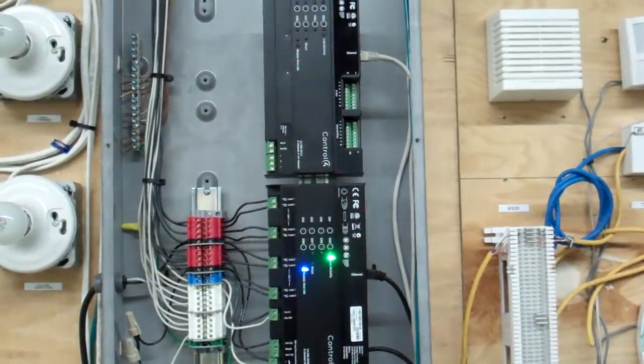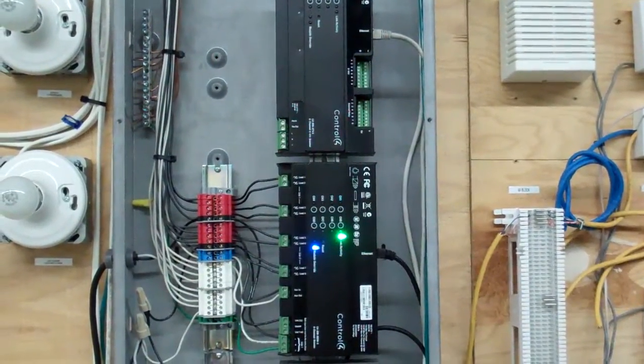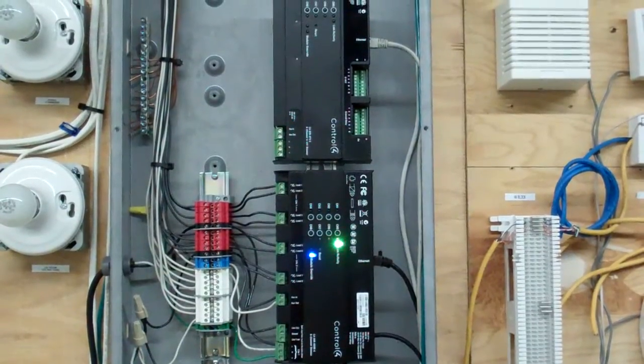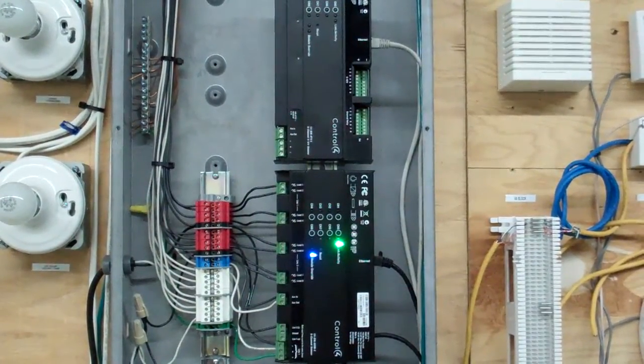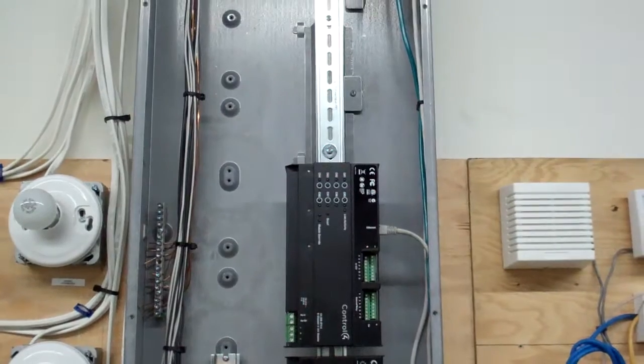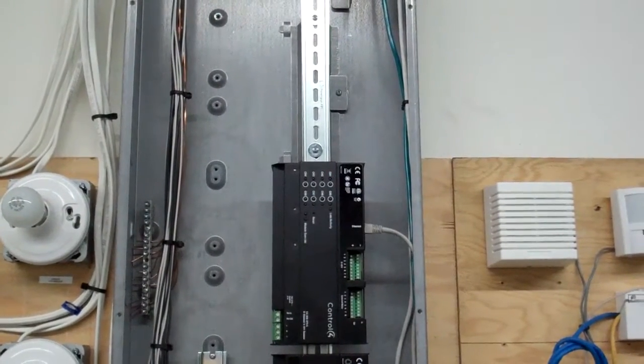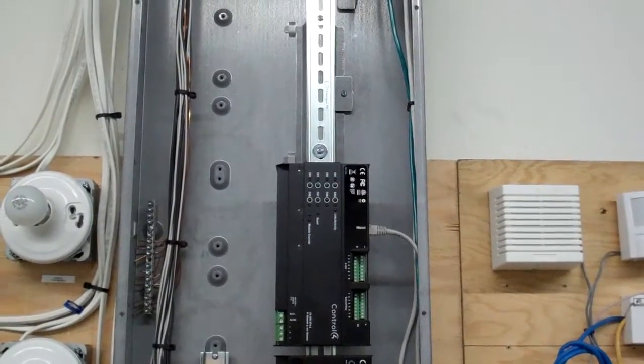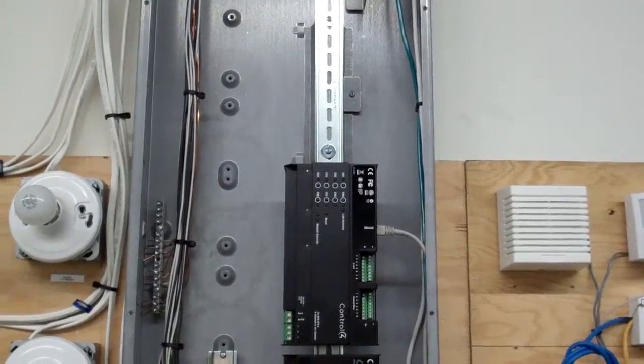And then above that, we have two of our lighting modules. The one at the bottom is an adaptive phase module that can handle forward or reverse dimming. And the one above that is our LED module that can send out a 0 to 10 volt communication, but can also work with external transformers as well.